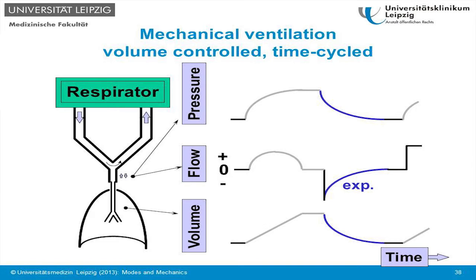When you have a flow sensor, you can also use volume controlled ventilation, which means that the ventilator does not set a certain pressure, and the air that goes into the patient's lung is determined by the pulmonary compliance, but the other way around. You set a certain tidal volume you want to apply to the patient, and then the ventilator will apply as much pressure as needed to generate exactly the tidal volume that was preset. And this means that the respirator can adjust to changing pulmonary compliance.